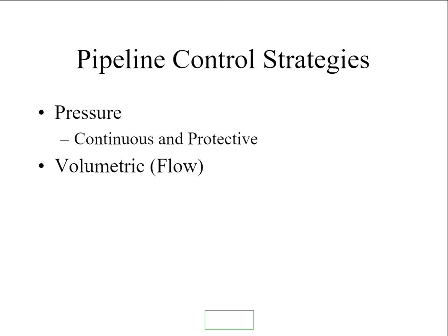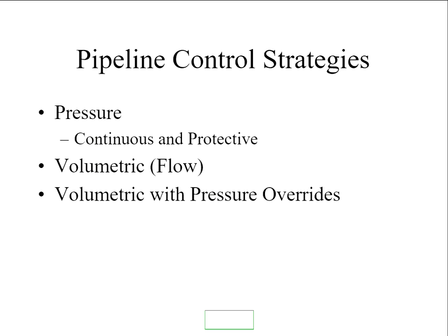Volumetric or flow control: if you want to manage the rate of transfer of flow from one system to another and let the pressure vary, you use volumetric control. But volumetric control often comes with pressure overrides, i.e. I'm quite happy to let the pressure vary, but it can't go above that and it can't go below that. So the pressure override will kick in and protect the downstream system from either seeing too much or equally too little, i.e. there's not enough pressure to maintain all the subsequent stages of supply.